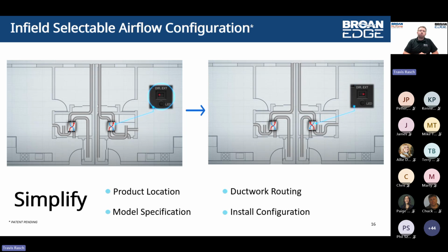Do know, not if, but when this indicator switch, the red switch there, isn't properly put in the right spot, our product is smart enough, for lack of a better term, to sense what the actual outdoor air condition is and ultimately make the internal adjustments accordingly to continue to operate the way it was meant to operate. Again, I'm not encouraging anybody to not set the switch in the right location. I'm simply letting everybody know not if, but when that switch isn't properly put in the right position, the product does have the integrated intelligence to detect what the actual outdoor airflow is and make those adjustments accordingly inside.